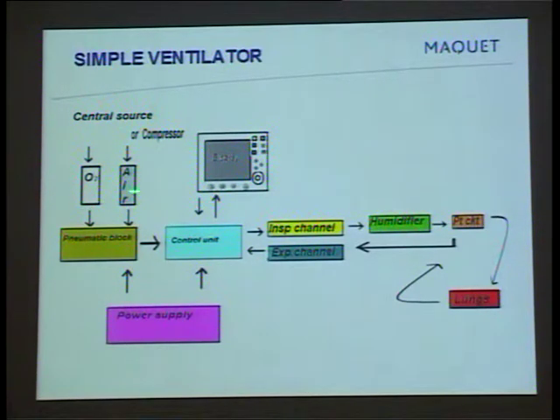But the reason we need to connect both air and oxygen is, if you connect only oxygen, it is pure oxygen. It is not possible to reduce the percentage of oxygen. Suppose the patient doesn't require 100% oxygen, it is not possible to reduce it. That is the reason we connect both air and oxygen, a combination. If you connect both, it is possible to keep whatever percentage the patient requires. Whatever pressures we get from the central source will be high pressures. It is not possible to deliver the same pressure to the patient's lung, or the lung will burst. So we need to reduce these pressures.